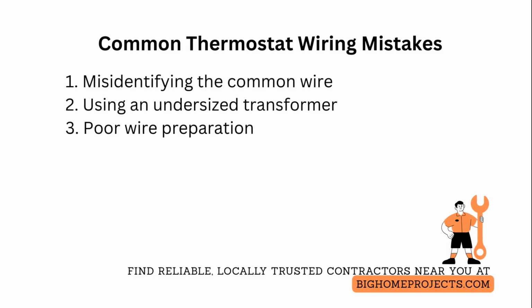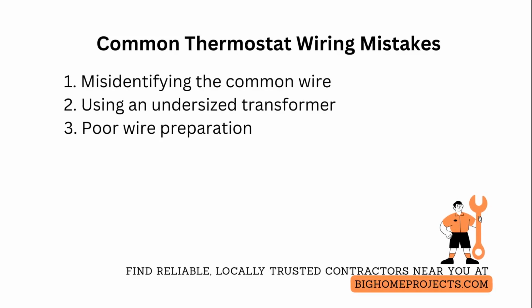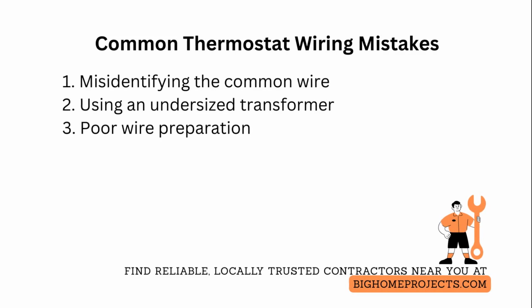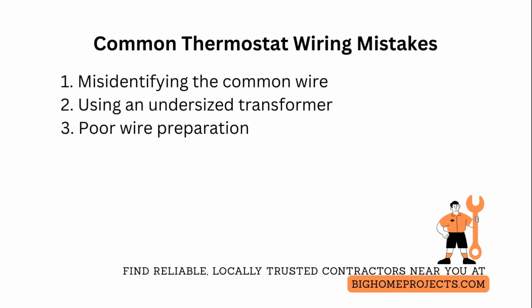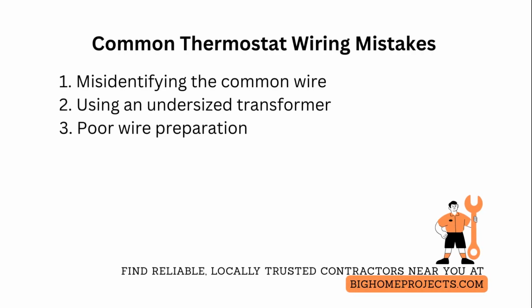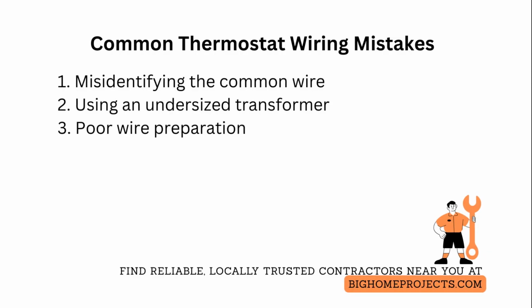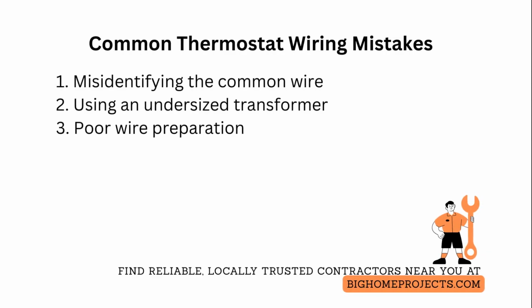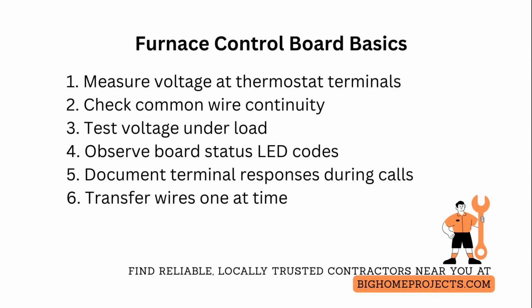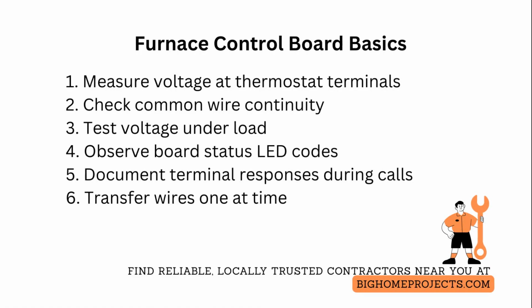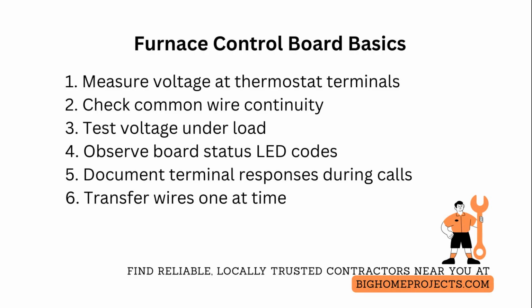Furnace control boards act as the system brain, taking low-voltage thermostat signals and sequencing ignition, blower, and fan speeds so homeowners can diagnose and replace thermostats with confidence. The control board receives the thermostat's low-voltage calls, heat, cool, fan, and translates those into timed outputs for inducer motors, gas valves, igniters, and blower relays.